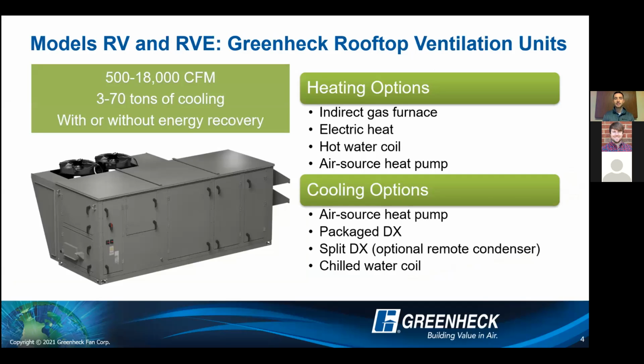From an overall capacity standpoint with the RV and RVE, you're looking at 500 to 18,000 CFM. So wide range of CFMs there, anywhere from 3 up to 70 tons of package cooling with or without energy recovery. So obviously sliding the energy wheel upstream of all your cooling and heating and downsizing that accordingly. And then from heating and cooling options, so we do have the indirect gas furnace, electric heat, hot water coil. We have the air source heat pump from 5 up to 30 tons, if that is something that you see in your area at all.